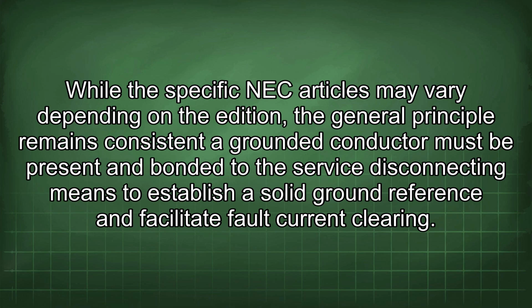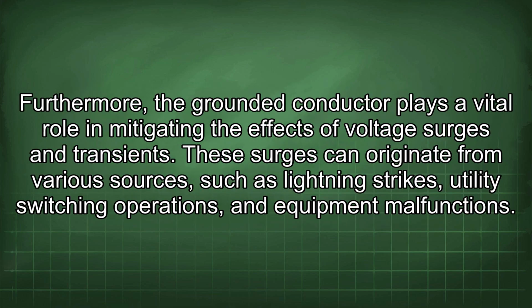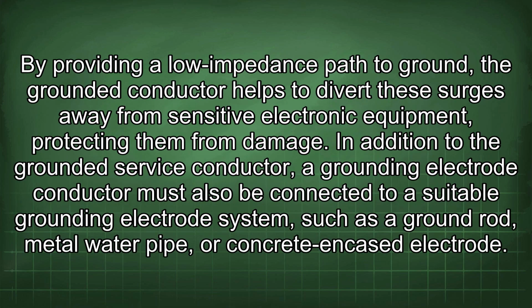A grounded conductor must be present and bonded to the service disconnecting means to establish a solid ground reference and facilitate fault current clearing. Furthermore, the grounded conductor plays a vital role in mitigating the effects of voltage surges and transients. These surges can originate from various sources, such as lightning strikes, utility switching operations, and equipment malfunctions. By providing a low impedance path to ground, the grounded conductor helps to divert these surges away from sensitive electronic equipment, protecting them from damage.